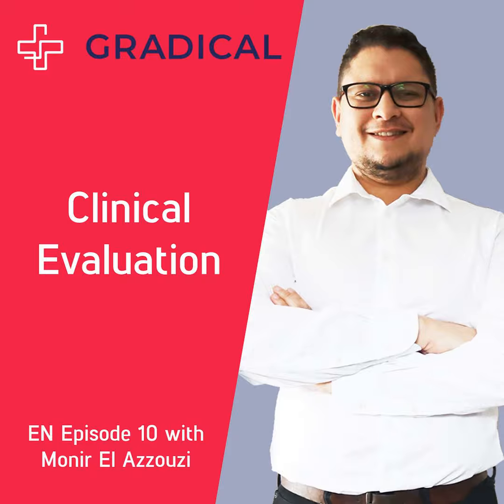You have certain listed devices in the EU MDR, for example screws, plates, braces, wedges, etc. A lot of things are listed. If it is this kind of technology, which is also implantable, it's called well-established technology, and then it doesn't need too much clinical data because we have enough data about it. As I said, they are listed, but there is also a definition of what a well-established technology is. If you can prove that your device is used since many years, and has never had any problem, then you can mention that.